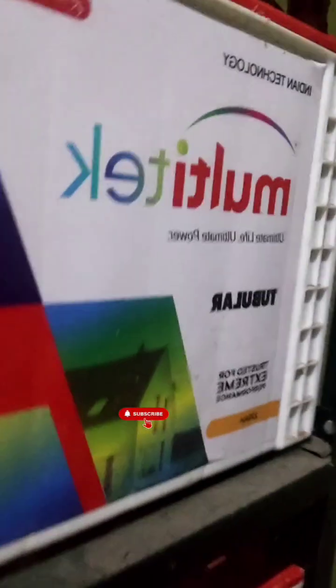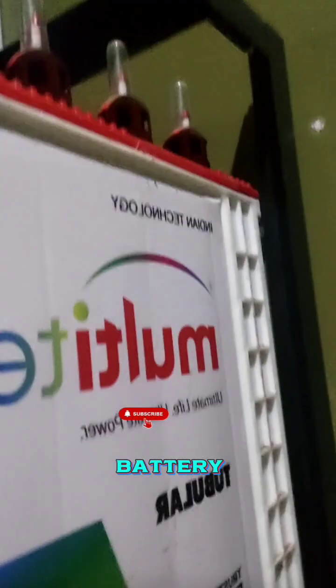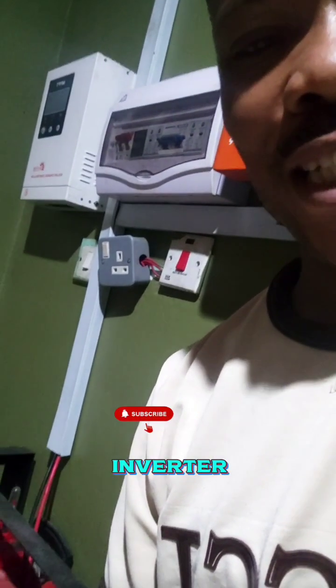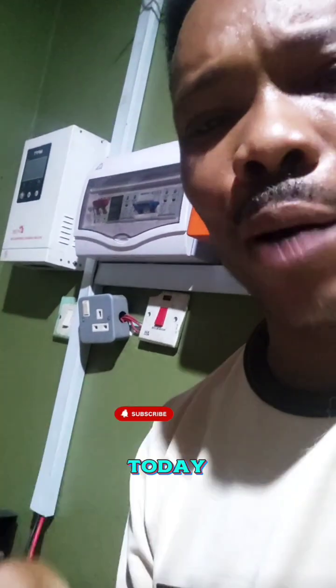This is 4 batteries of 220 ampere each. Each of them is 220 ampere, and there are 4. Because I have a 6 kVA inverter, that does not mean I can use it and abuse it. So let's go into calculation. Today we are going to do a calculation together to know the required load we are supposed to put, or how long our load will affect the availability of our setup.